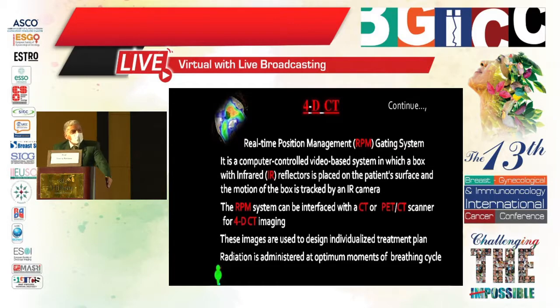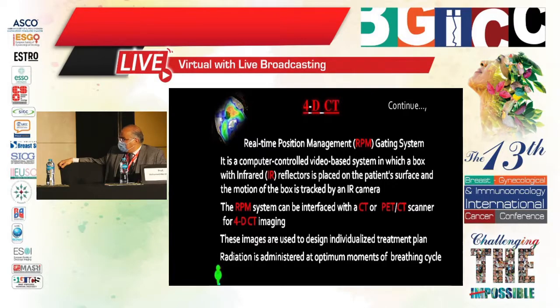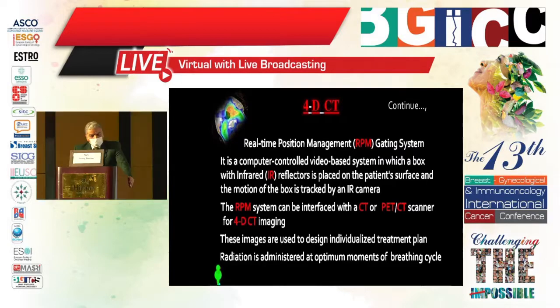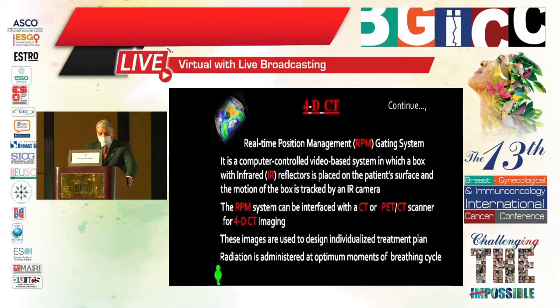The 4DCT real-time position management (RPM) gating system is a computer-controlled, video-based system in which a box with infrared reflectors is placed on the patient surface and the motion of the box is tracked by an infrared camera. The RPM system can be interfaced with a CT or PET-CT scanner for 4DCT imaging. These images are used to design an individualized treatment plan, and radiation is administered at optimum moments of the breath cycle.